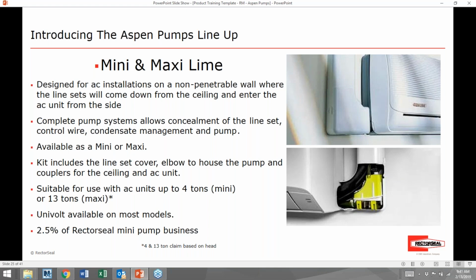Again, they're available in both a Mini and a Maxi, and the kit includes everything needed, including the line set cover, the elbow to house the pump, the couplers to connect the pieces of line set to both the ceiling and the unit. Again, these are suitable for 4-ton units on the Mini and up to 13 tons on the Maxi, and most of the Mini Lime product is available in a univolt. The Lime series only makes up about 2.5% of the Rector Seal business.